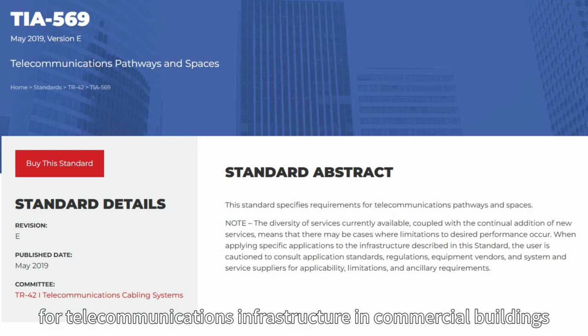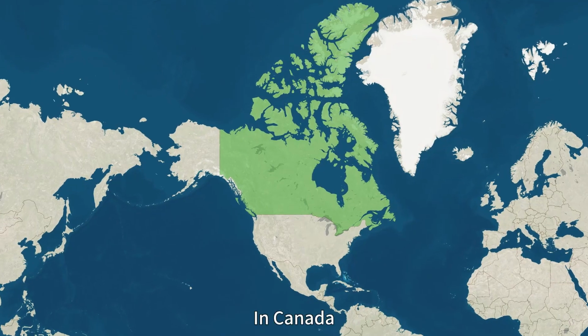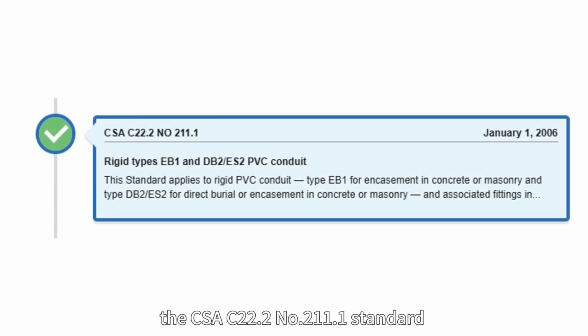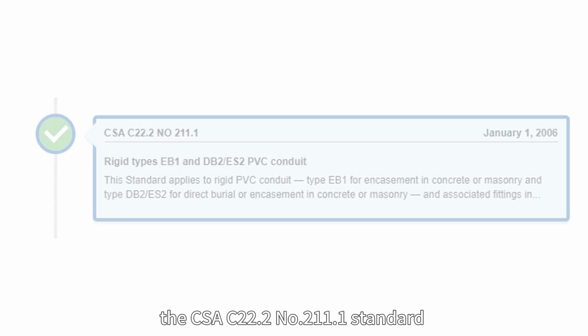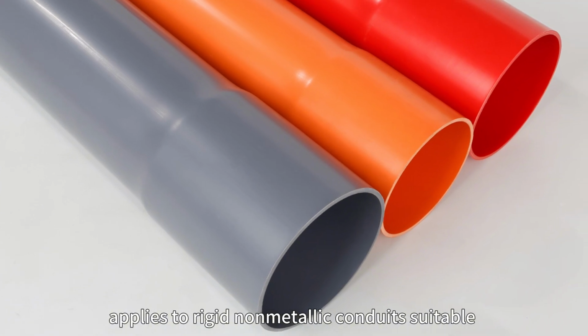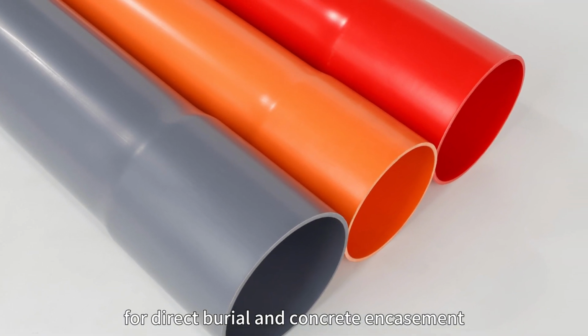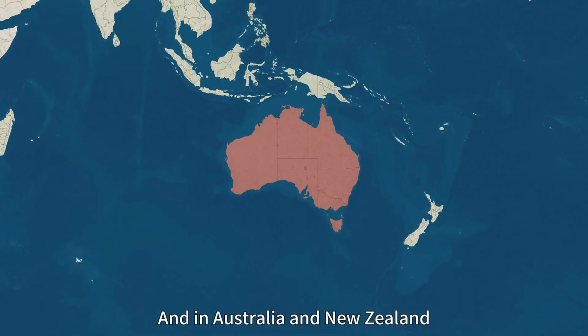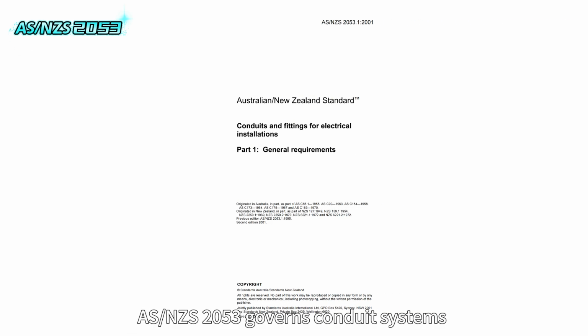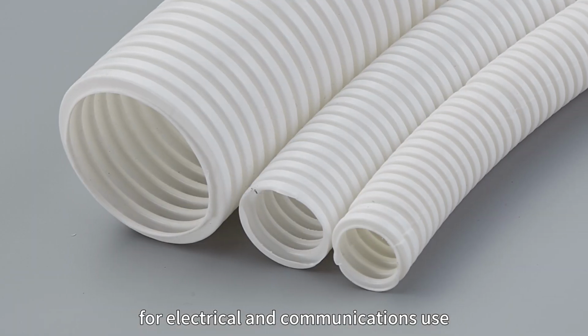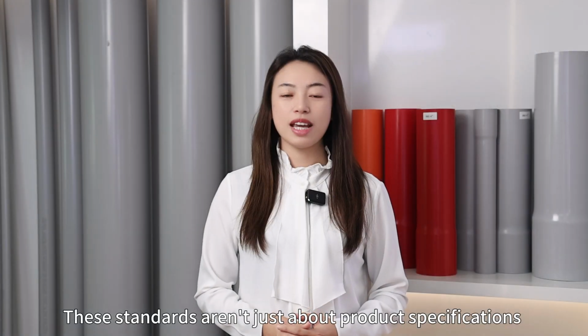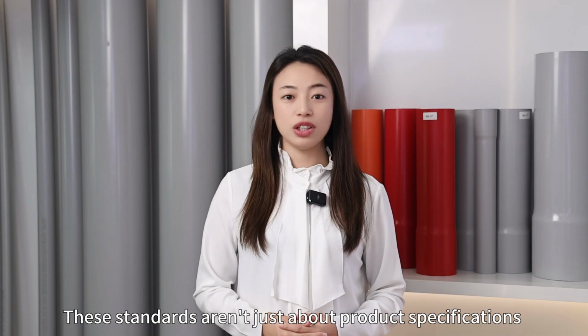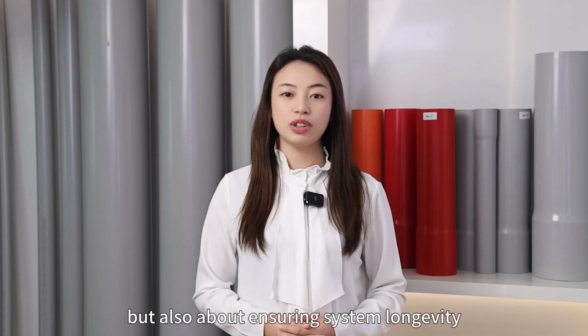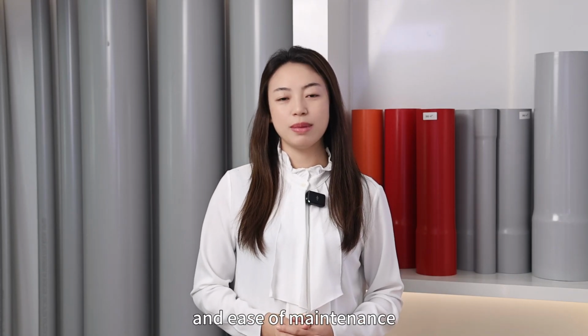and pathways for telecommunications infrastructure in commercial buildings. In Canada, the CSA C22.2 No. 211.1 standard applies to rigid PVC conduit suitable for direct burial and concrete encasement. And in Australia and New Zealand, AS/NZS 2053 governs conduit systems for electrical and communications use. These standards aren't just about product specifications, but also about ensuring system longevity, personal safety, and ease of maintenance.